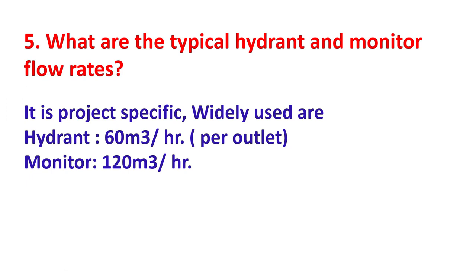What are the typical hydrant and monitor flow rates? It is project specific. Widely used values are: for a hydrant, 60 cubic meters per hour per outlet; for a monitor, 120 cubic meters per hour.